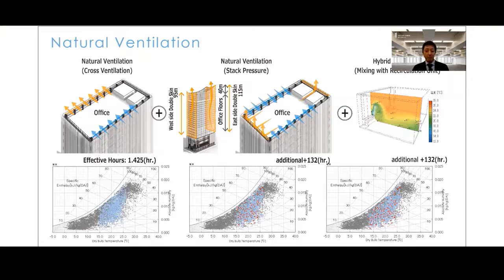The outdoor air temperature range between 15 and 26 degrees C is considered to be the best condition for natural ventilation. Especially on the low side, intake air may become uncomfortable when diffused into the space directly. To mitigate this concern, diffusers of the recirculation VRF units were allocated adjacent to those for outdoor air intake. In this way, the effective period of natural ventilation is further expanded.